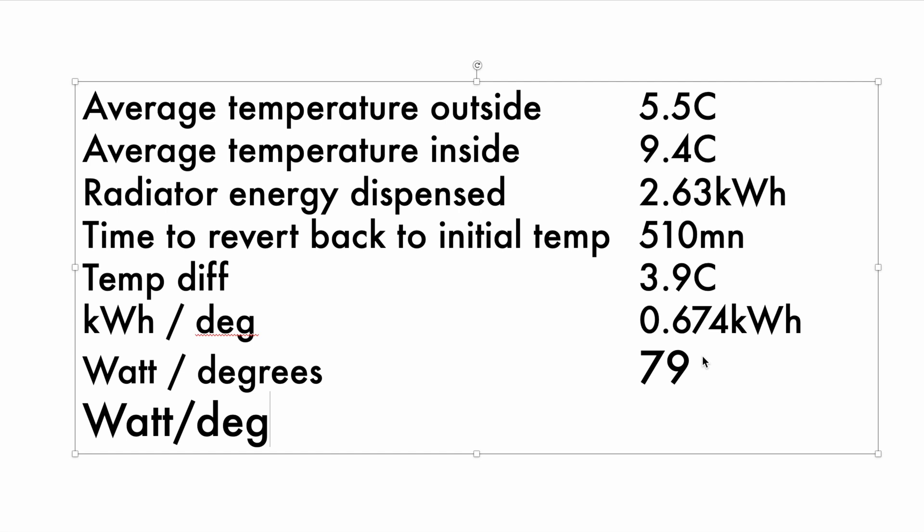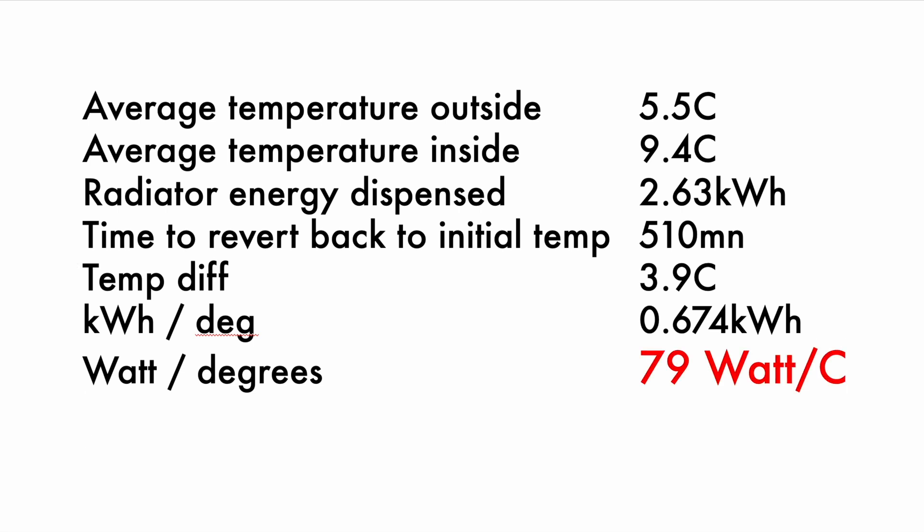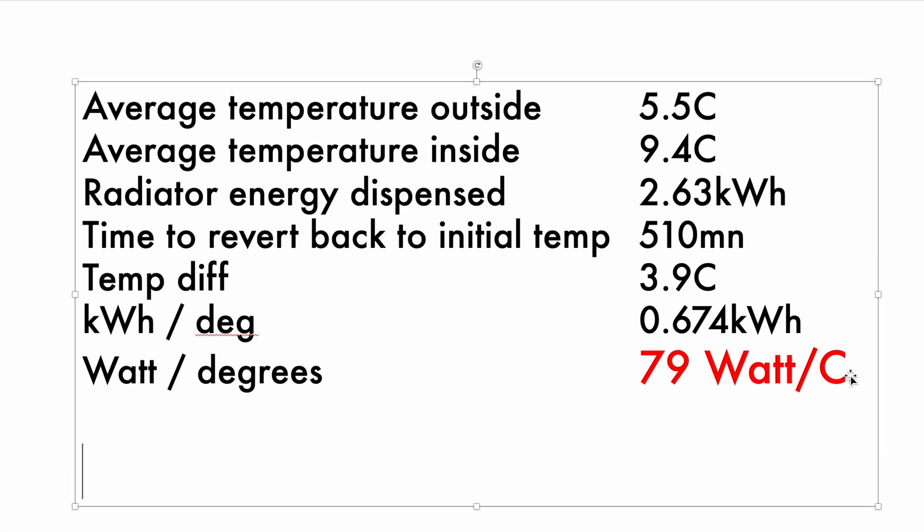That comes to about 79 watts. So our answer is: this room consumes about 79 watts for each and every degree of temperature difference we are trying to maintain with the external temperature. The more difference there is with outside, the more it's going to cost in energy.